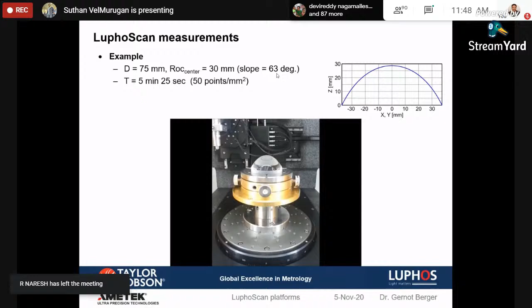So it collected the data for the entire 3D surface. This slope is approximately 63 degrees, and still we can measure the entire surface, but this may be a limitation in the contact profiler. We may have to tilt the sample, or we may have to tilt the traverse unit. So here we need not tilt anything, because we have a tilt option in the probe itself. So the probe can tilt according to the slope of the part and collect the data.